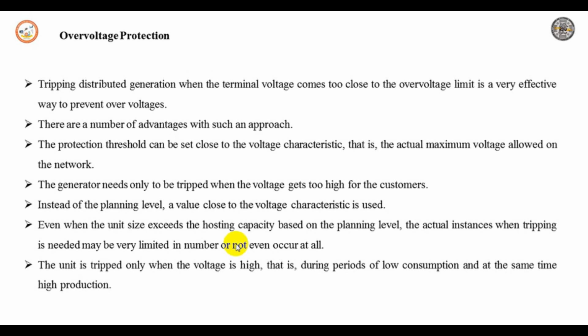Tripping of a distributed generator when the terminal voltage comes very close to the over voltage limit is a very effective way of preventing over voltage. There are a number of advantages with such an approach. The protection threshold can be set close to the voltage characteristics, that is, the actual maximum voltage allowed on a network. The generator needs only to be tripped when voltage gets too high for the customers. Instead of the planning level, a value close to the voltage characteristics is used. So when unit size exceeds the hosting capacity based on the planning level, the actual instances where tripping is needed may be very limited in number or not even occur at all.